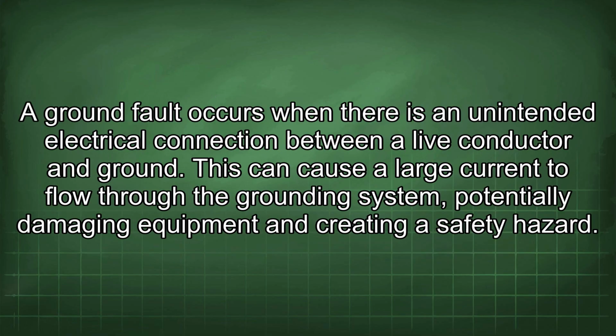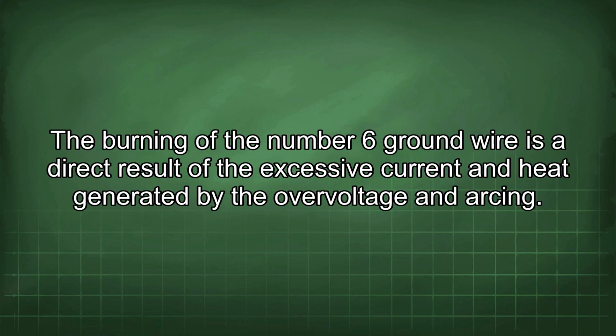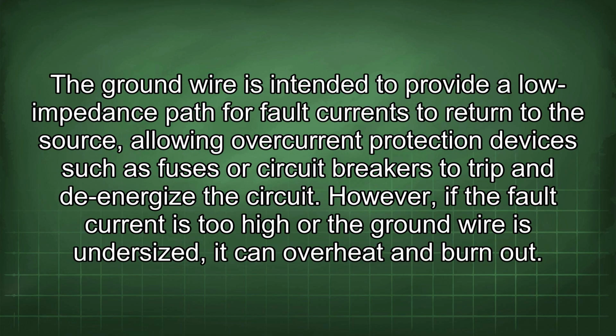A ground fault occurs when there is an unintended electrical connection between a live conductor and ground. This can cause a large current to flow through the grounding system, potentially damaging equipment and creating a safety hazard. The burning of the number 6 ground wire is a direct result of the excessive current and heat generated by the overvoltage and arcing. The ground wire is intended to provide a low impedance path for fault currents to return to the source, allowing overcurrent protection devices such as fuses or circuit breakers to trip and de-energize the circuit. However, if the fault current is too high or the ground wire is undersized, it can overheat and burn out.